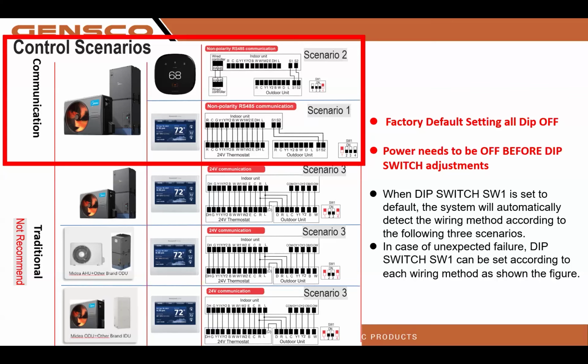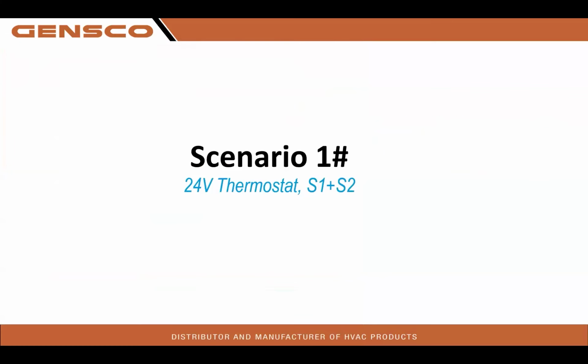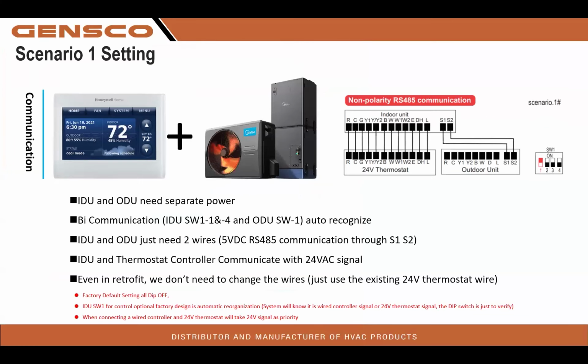2 wires to the indoor, 2 wires to the outdoor. In the event that you wanted to use a different stat, make sure that we are able to set cycles per hour to 1 on the compressor. And look at this scenario here. We've got a 24-volt stat connected 24-volt to the indoor unit and only 2 wires going out to the outdoor unit. In that scenario, we are going to turn on dip switch SW1 to auto recognize.